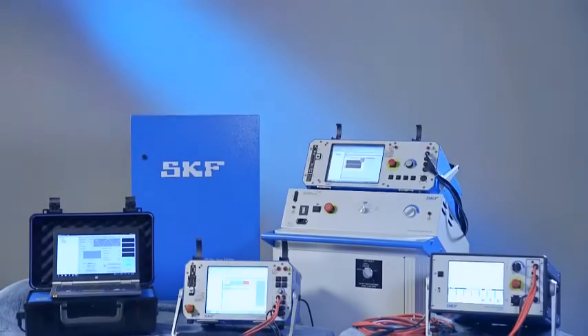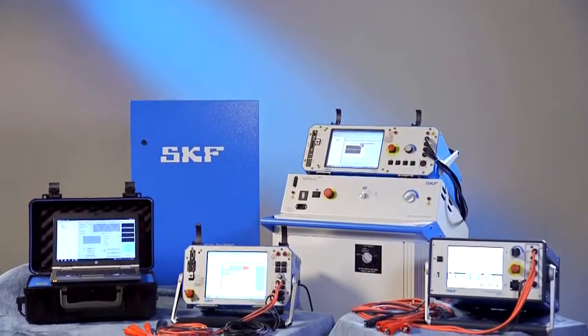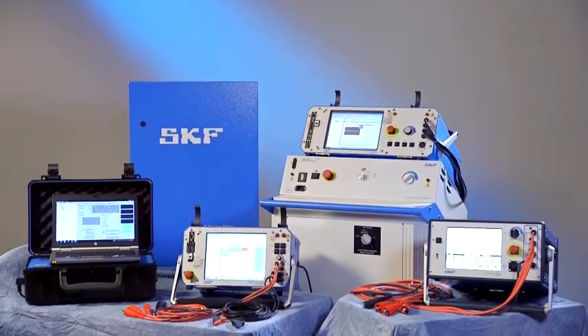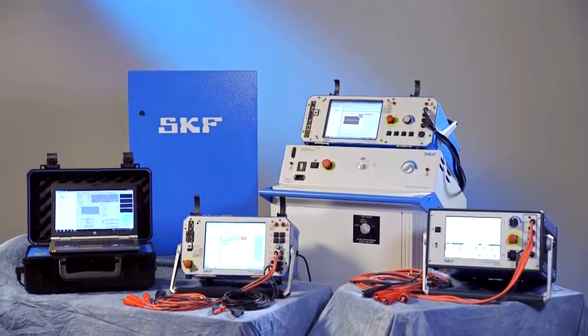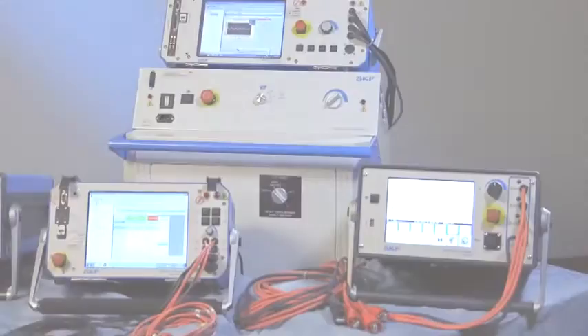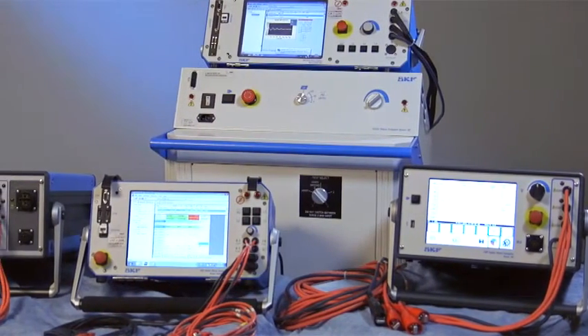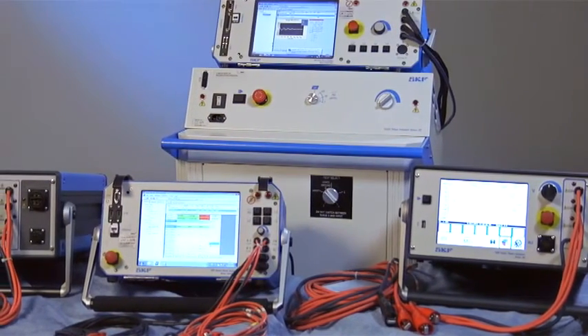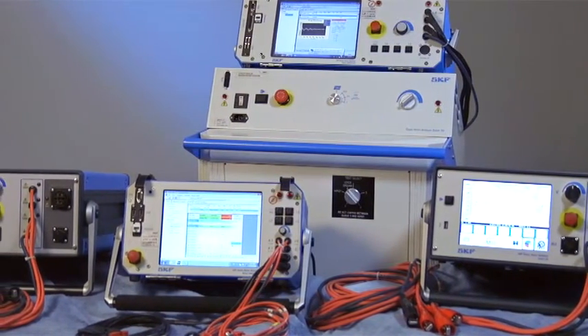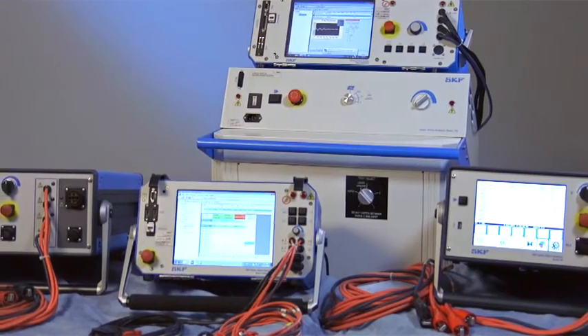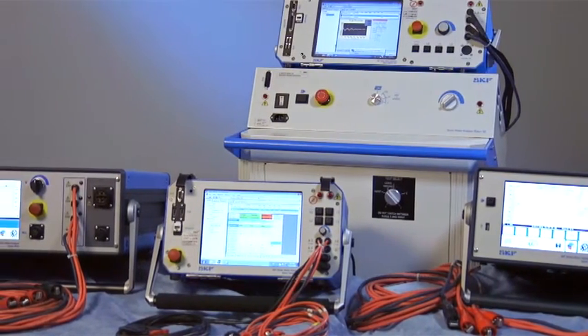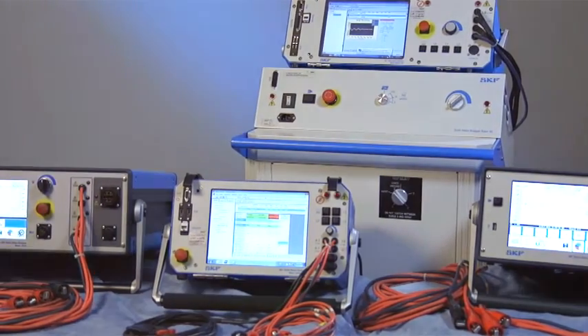SKF electric motor condition monitoring solutions completely address the faults not covered by vibration monitoring. SKF static motor testers completely assess the insulation system of the motor. These tests are run when the motor is off, disconnected from the AC power source.